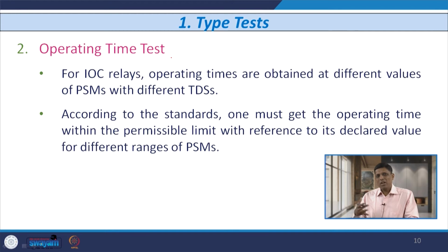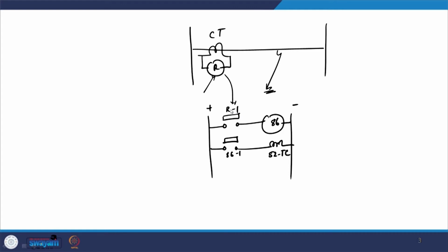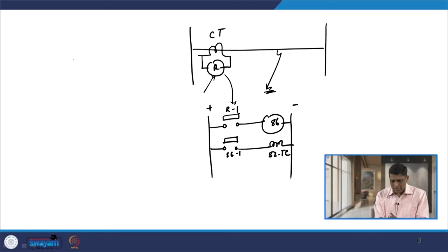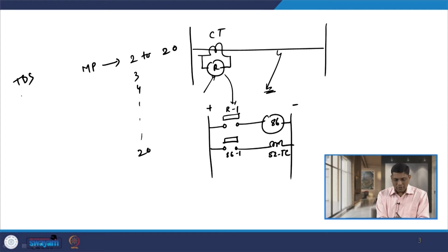So, for all inverse time overcurrent relays, the operating time is obtained for different values of plug setting multipliers, or multiples of pickup current, with different values of TDS. When you consider this circuit, the multiple of pickup current, let us say, ranges from 2 to 20. So, you have to take 2, 3, 4 in steps of 1 up to 20, and then the other value, the TDS, say 0 to 1 in steps of, let us say, 0.05.